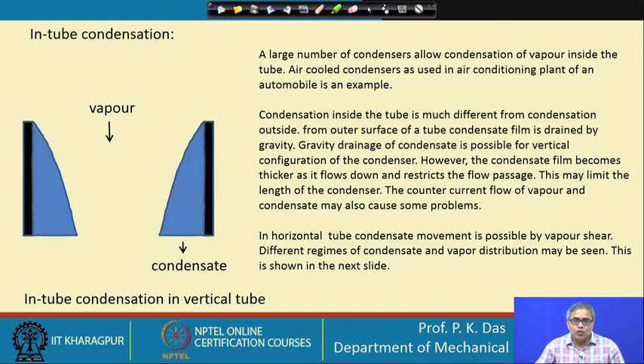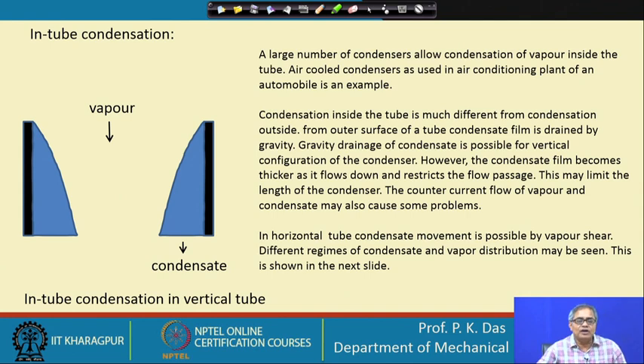There are many heat exchangers where horizontal tubes are used for the condenser and the vapour is inside these horizontal tubes. In this case, removal of condensate is needed, and generally vapour shear is used to do this. There will be enough pumping head supplied to the vapour so that vapour pushes the liquid, because since it is horizontal there is no advantage from gravity.